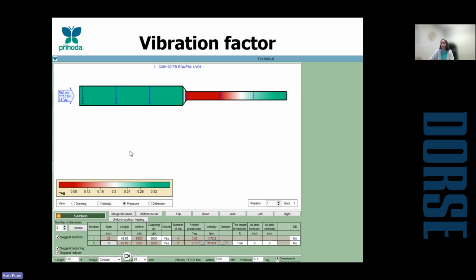So we can see here when we're looking at this chart that if we were to start out with like a 28-inch diameter and do something crazy, like reduce down to a 12-inch diameter, not only is this system indicating to us in this bright red, hey, that we're going to have a problem here, but it's also showing us down here on that chart what our problem is. So we know when we made that reduction there, that our inlet velocity shot up to almost 3,200 feet per minute. So we know specifically, hey, we're having a problem here.